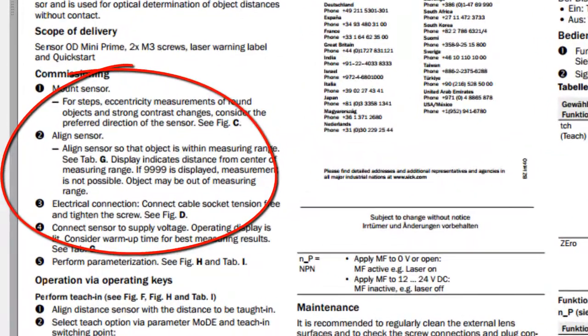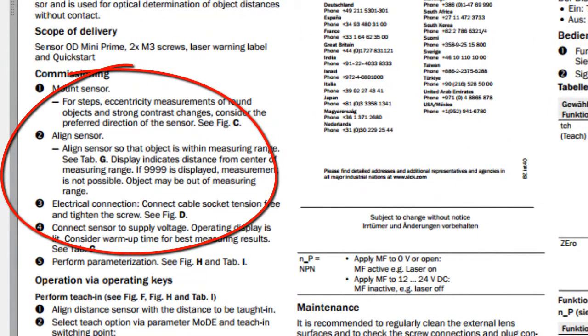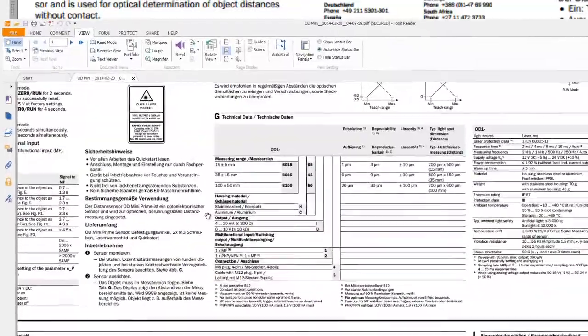We also need to align the sensor to a target that we're going to be measuring. And for that, take a look at the sensor, and it gives a span of the sensor from a minimum and maximum distance. Align it so that the target is somewhere in the middle of that range.